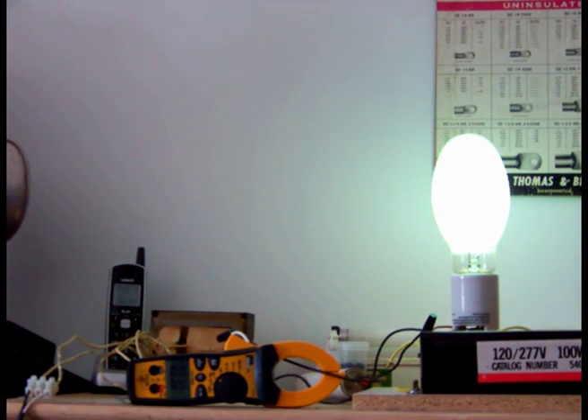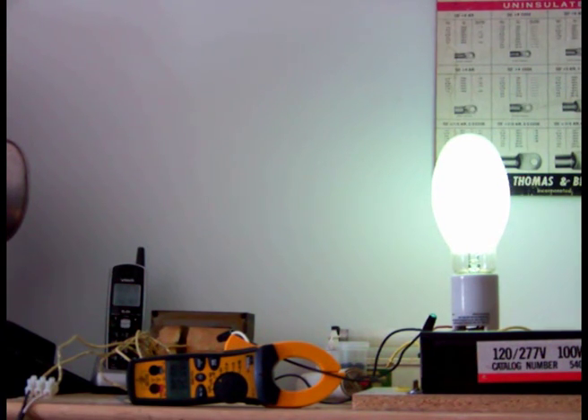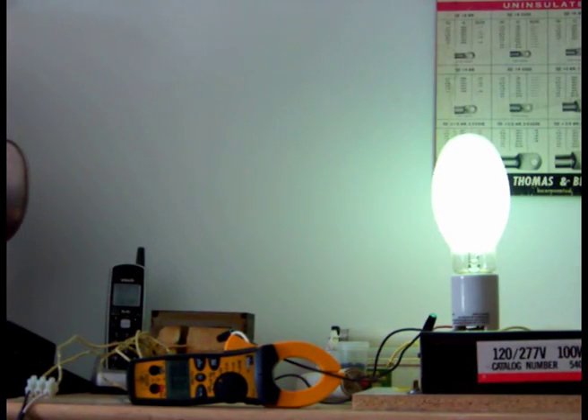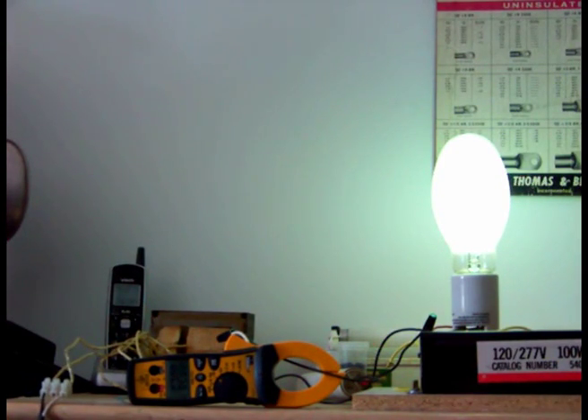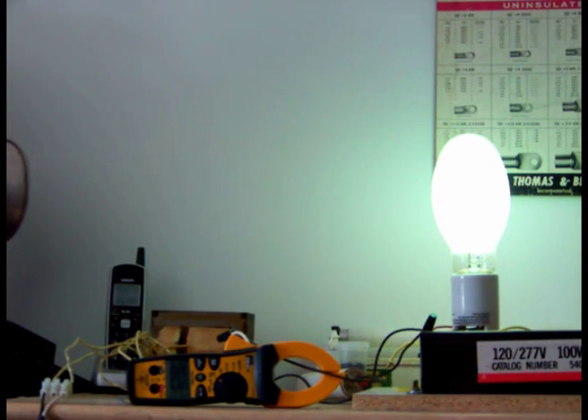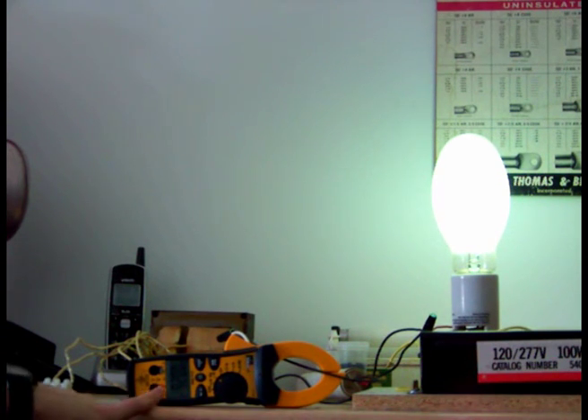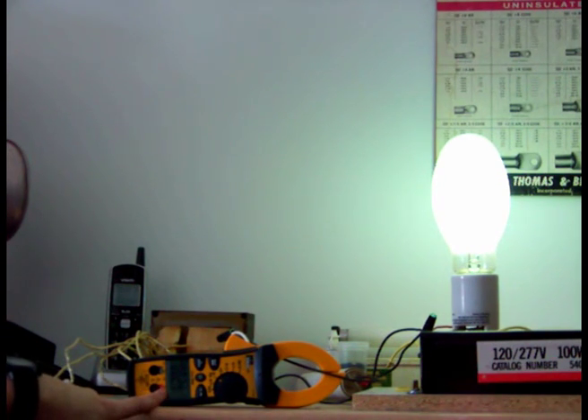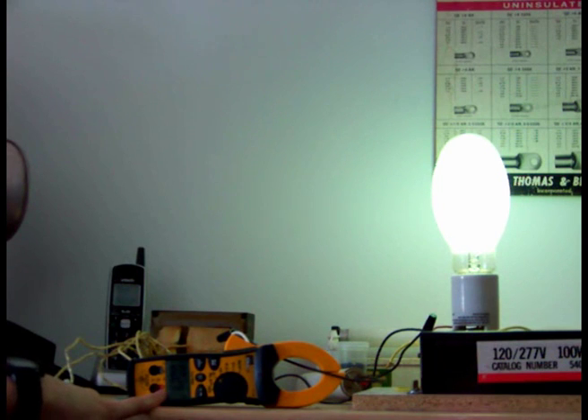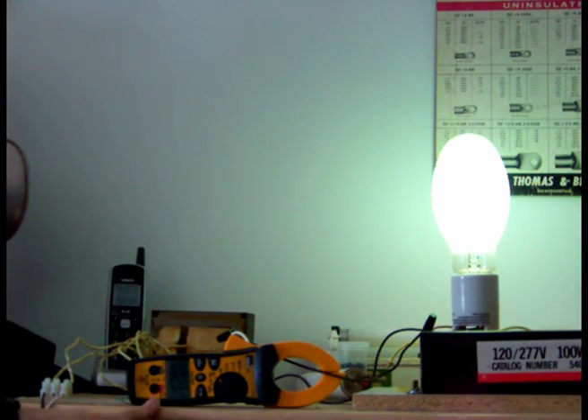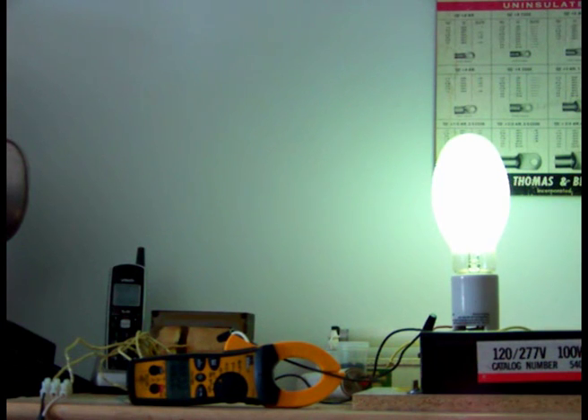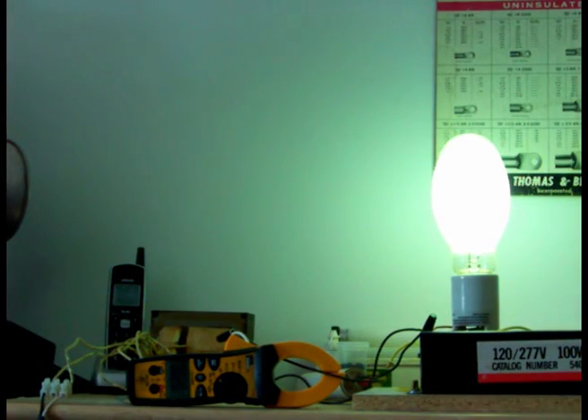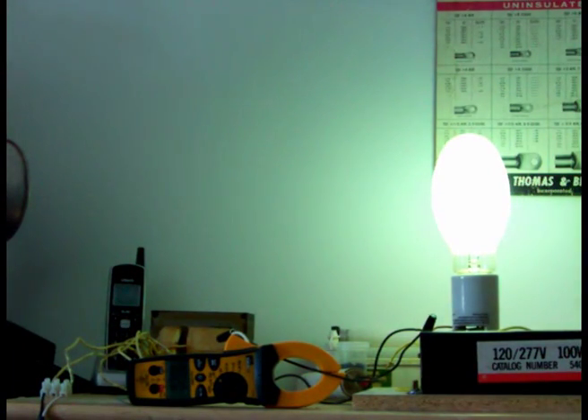But remember, with CWA ballast, I don't remember if I told in my videos, but with CWA ballast, the current value that doesn't change through the warm-up is the line current, and not the... Oh, see? Value goes down. We aim for 1.9 around that. So at the lamp, the value will start high and then go down. But the line current won't change. Which is different from a, say, HX ballast, in which even the line current will change.